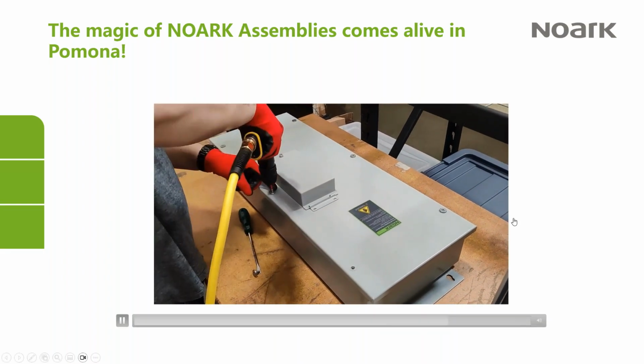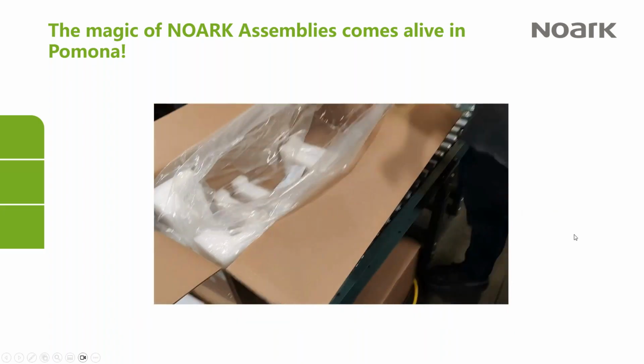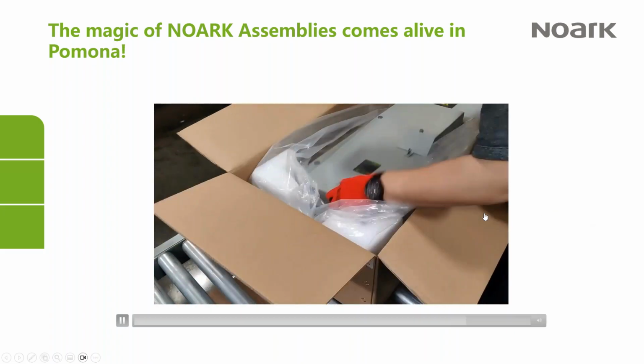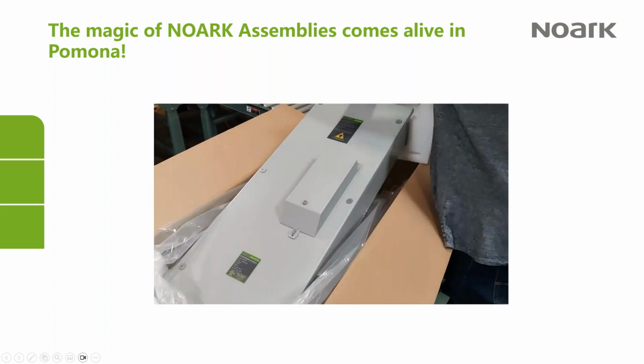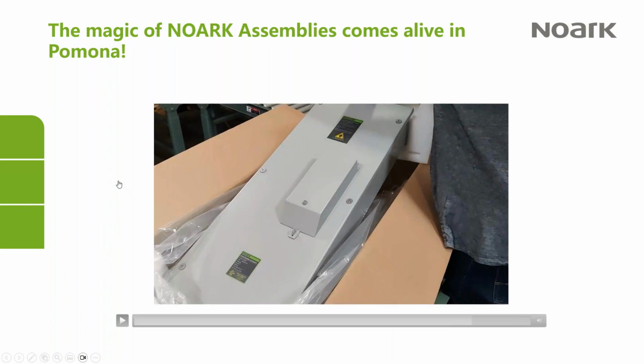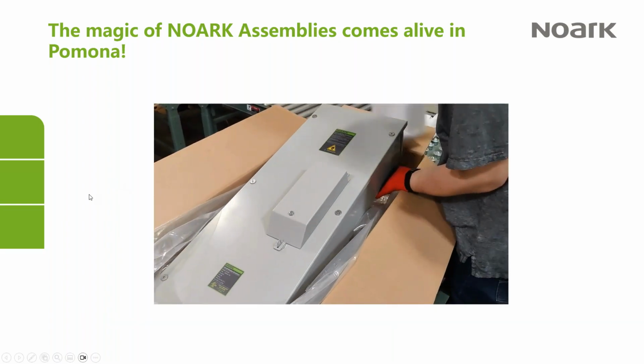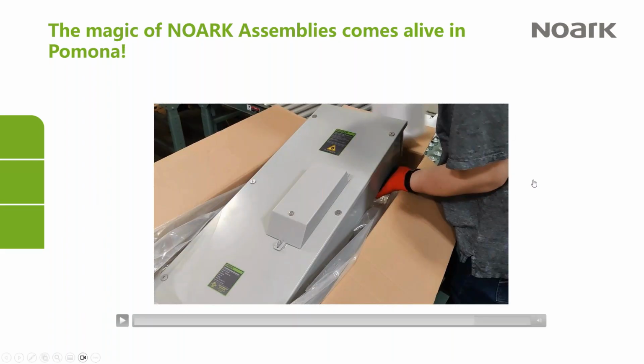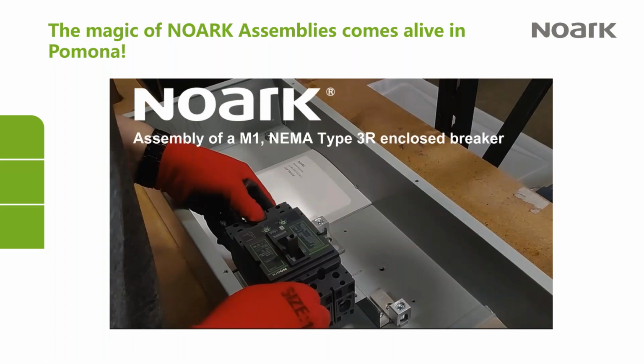Perfect. And regarding the neutrals, do the neutrals have bonding capability to ground for service entrance rating? I believe so. That's a technical question. I'll pass it on to Rob, but I believe so. Sorry, I had to shut the video off because the sound was drowning you guys out on my side. I'll cover this in a little more detail, but yes, there's a bonding provision for ground in the neutral assembly. Fantastic. And the last question we got throughout the video was, are the torque requirements for the fasteners and lugs given in the info? That's correct. Once we put all the instructions into the enclosure for the breakers and the neutrals, I'll have all the information there.